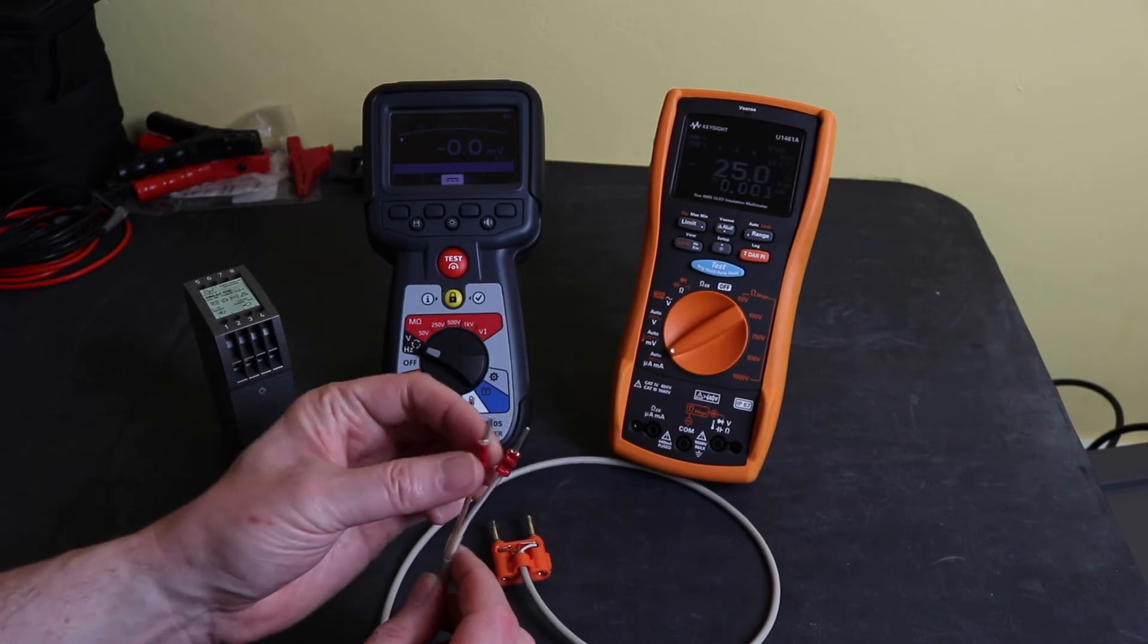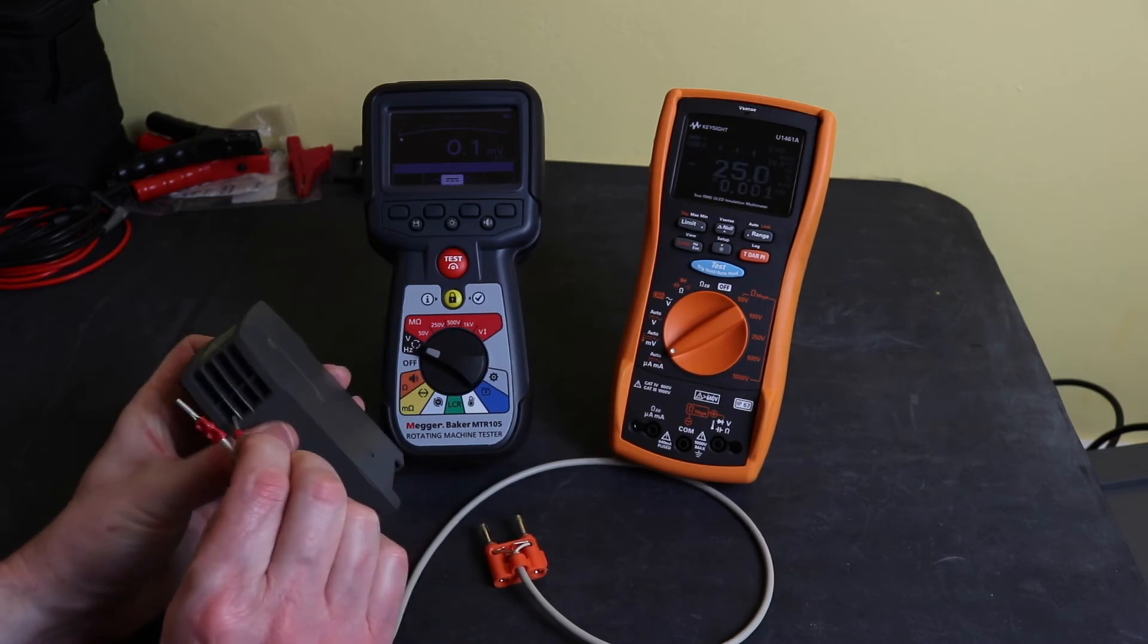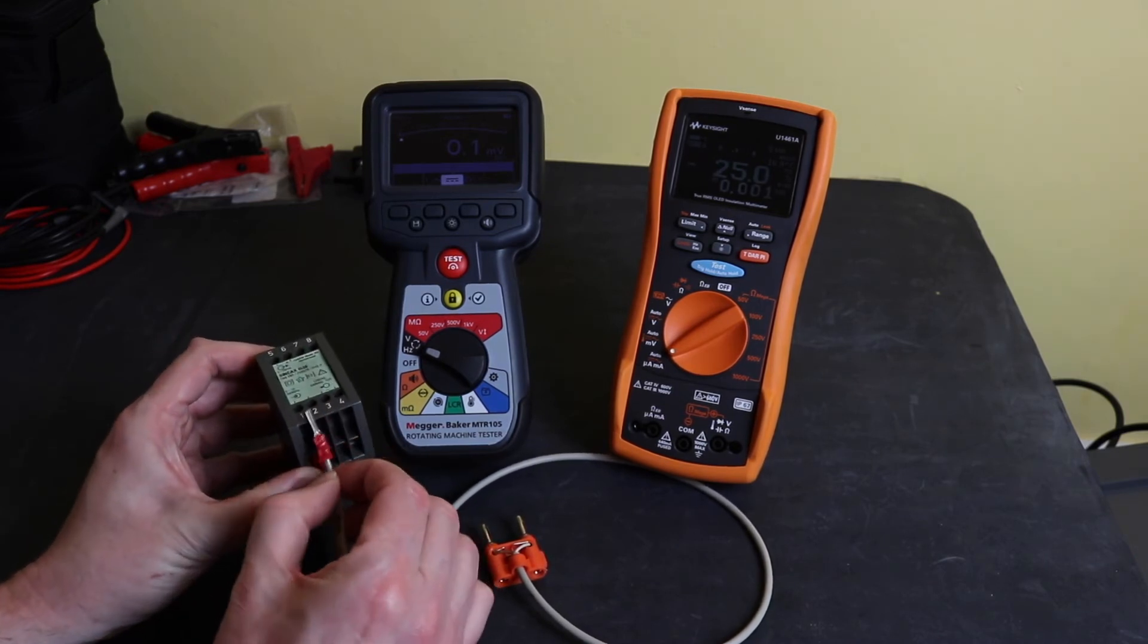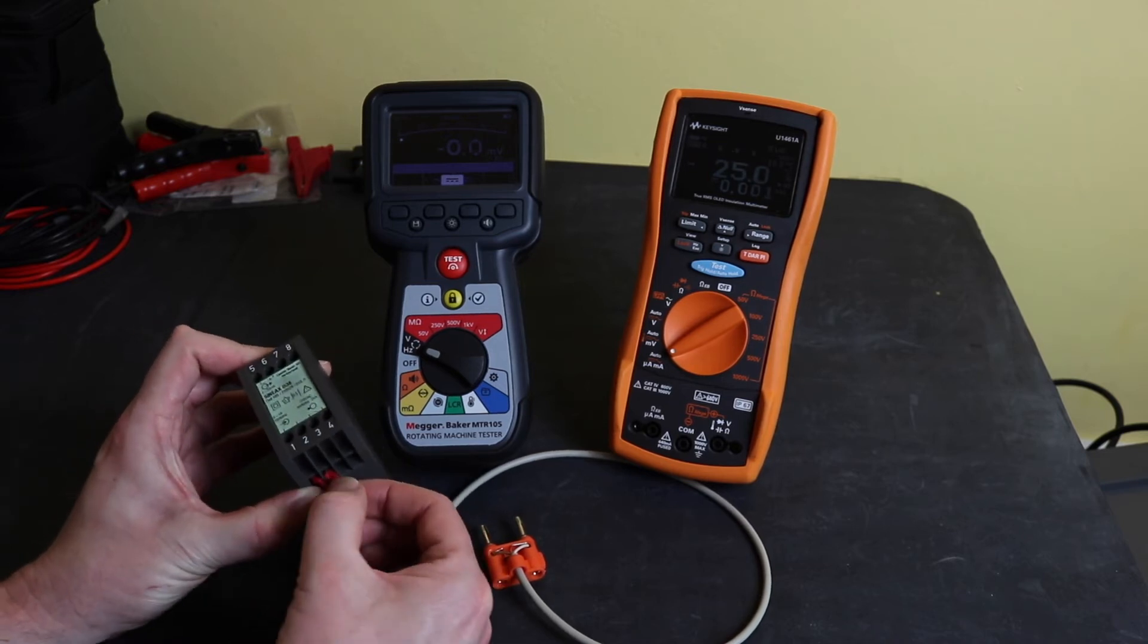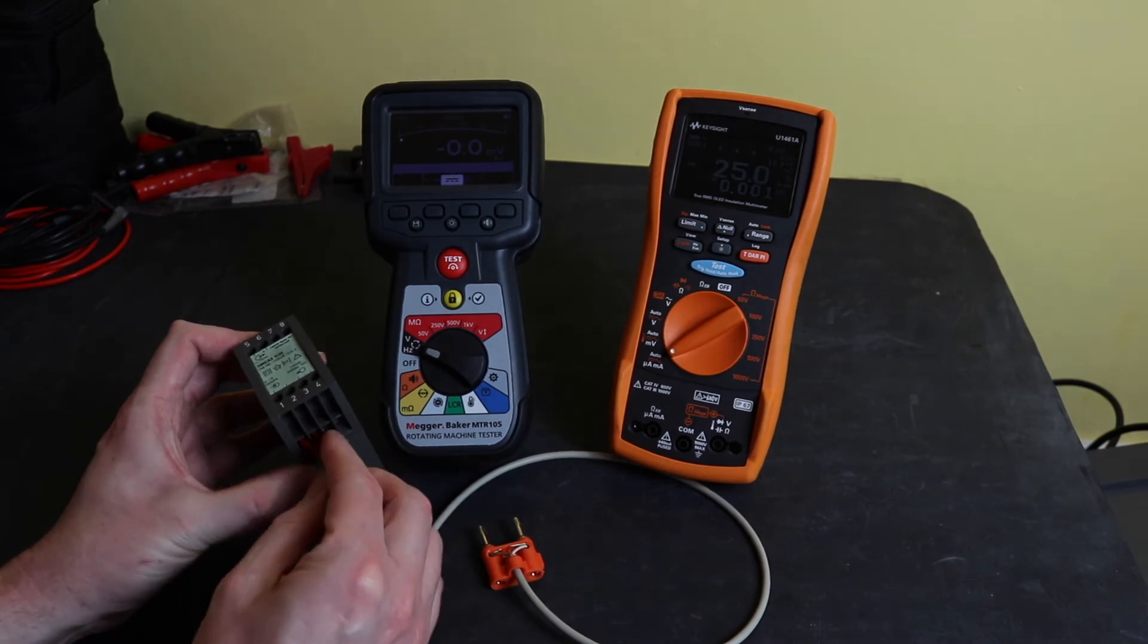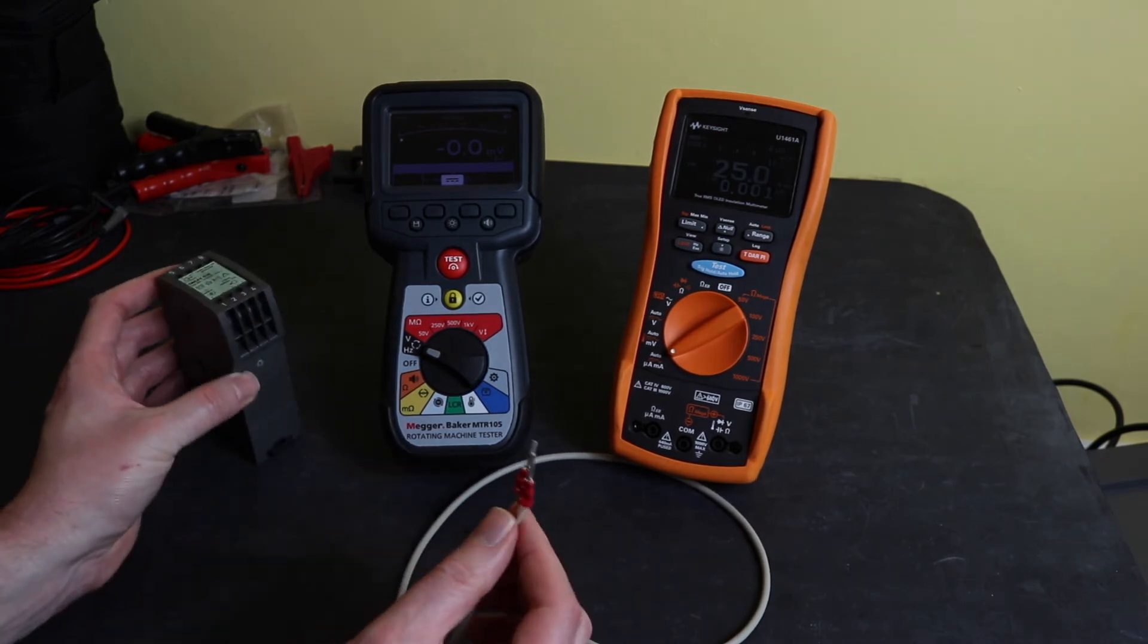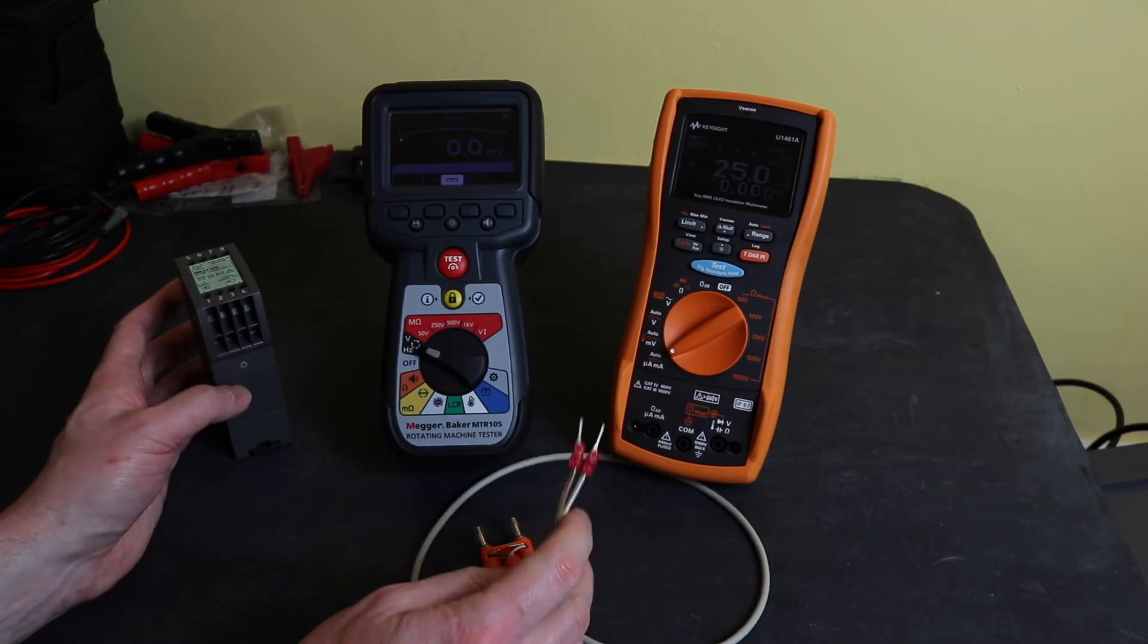I find these better to use than the ferrules for situations where you're constantly taking them in and out of terminals. They are a little bit bulky and you do have to slide them in on their side. They will just about go in but on some smaller terminals it won't. So you kind of have to put them in that way and they're fine but I find them much more robust than a ferrule so I tend to stick to those for this kind of setup.